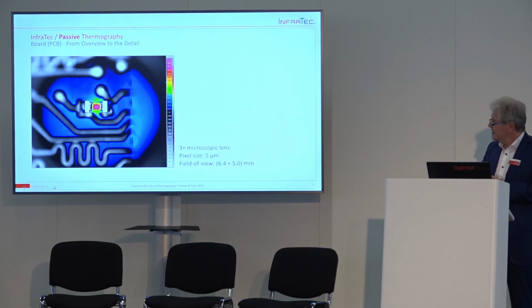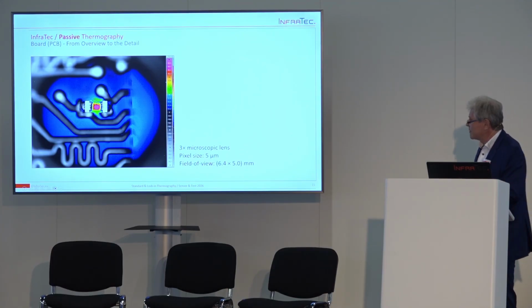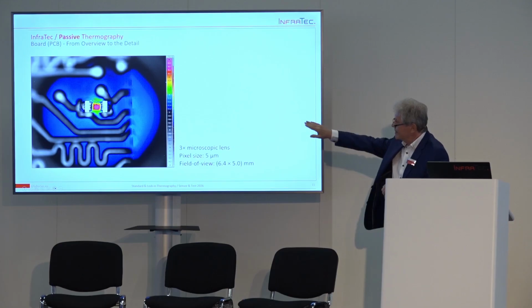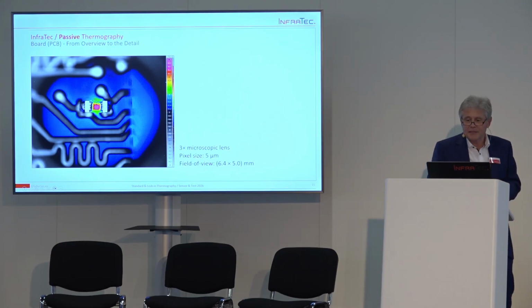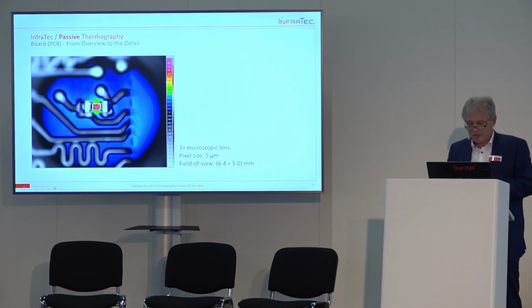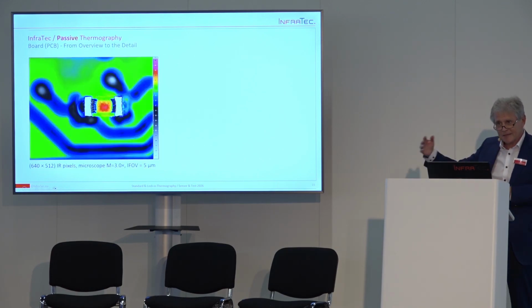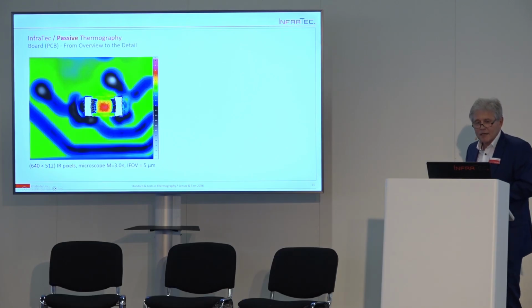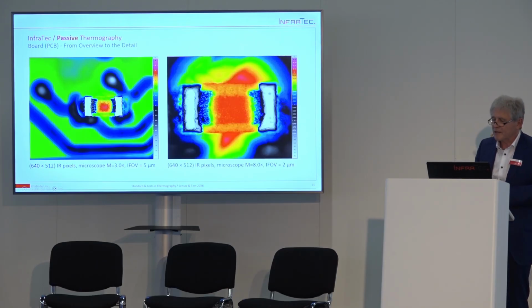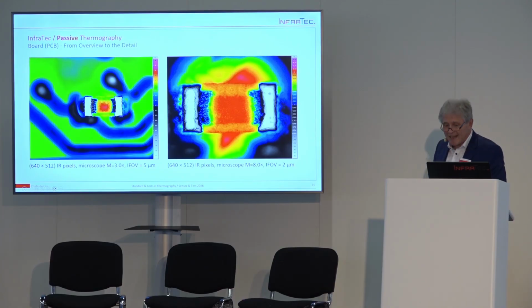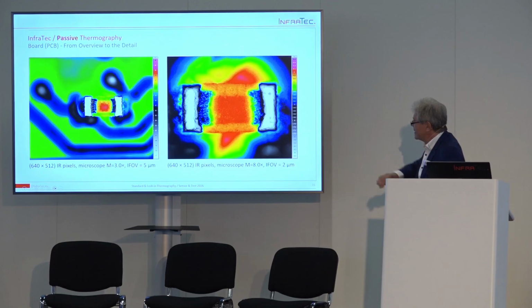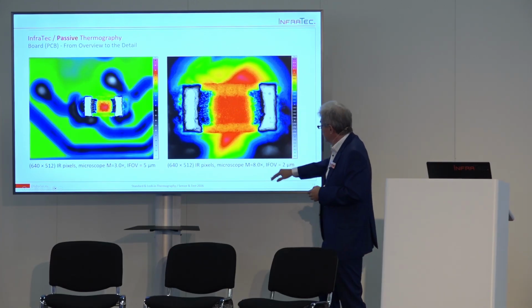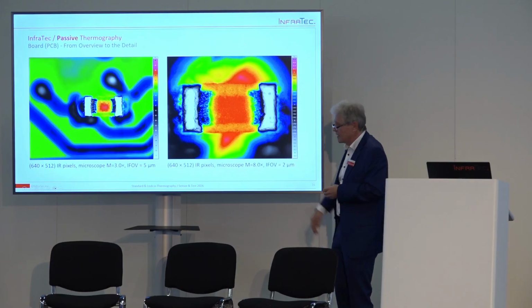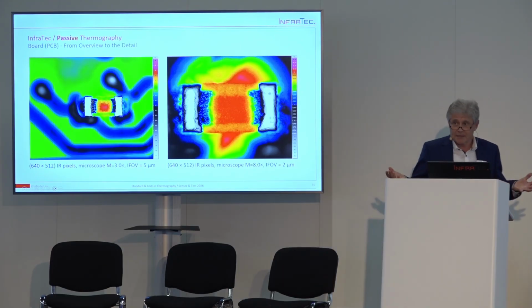So here's another part. Here's a small resistor, an image with a microscope lens with magnification factor 3. Here you see an image with a pixel size of 5 micrometers, field of view 6.4 by 5 millimeters. But it can be improved as well with the next step of microscope lens. This is the next image, with a magnification by factor 8. Here you see the temperature distribution of a resistor with magnification 8 and a pixel resolution of 2 micrometers. Okay, but this is standard.